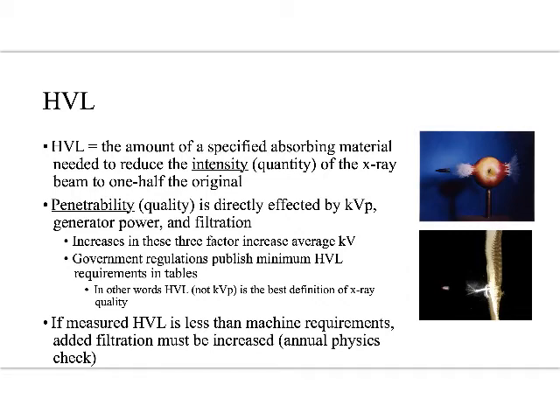What exactly are we saying with half value layer? We're measuring the intensity of this x-ray beam based on what it can penetrate. Can it get through an apple? Can it get through Kevlar? The harder the beam, the more it can get through. But we also wouldn't want to keep increasing KVP endlessly, because we're not trying to image Kevlar — we're trying to image something more like an apple. If everything gets through, there's no picture.